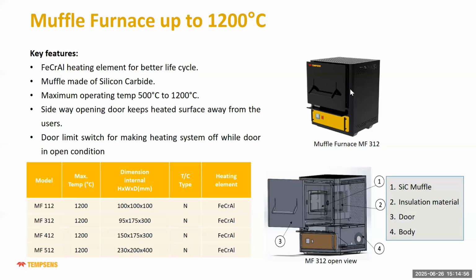It has a side door opening, so users are kept away from direct exposure to heat. We use a special type of limit switch, so whenever the door is opened, the heater will not get power. This is the MF312 open view. You can see the silicon carbide muffle, the insulation material, the door and the body.